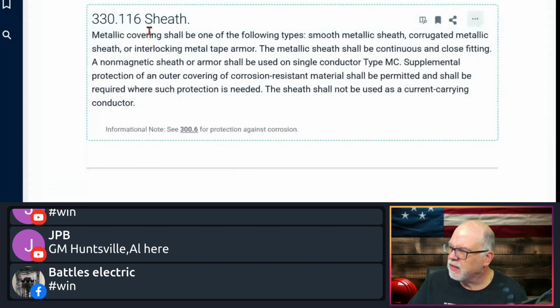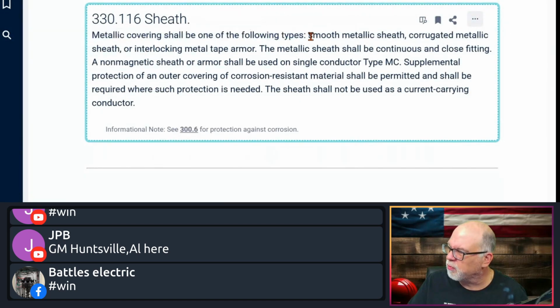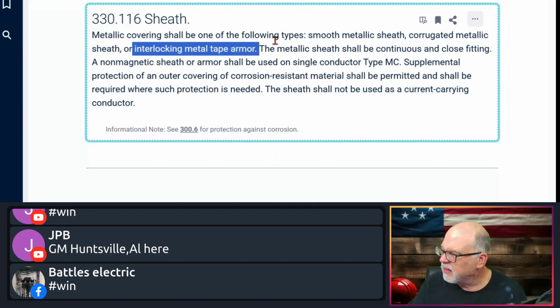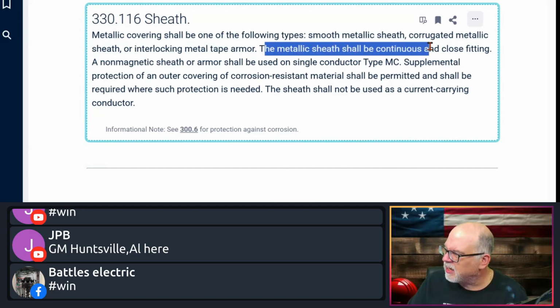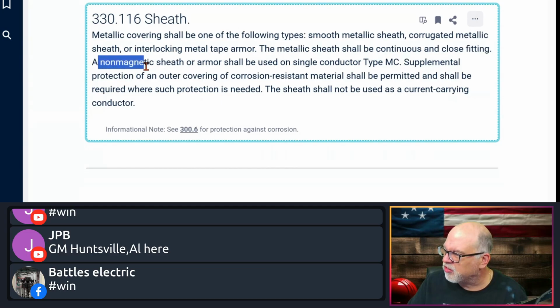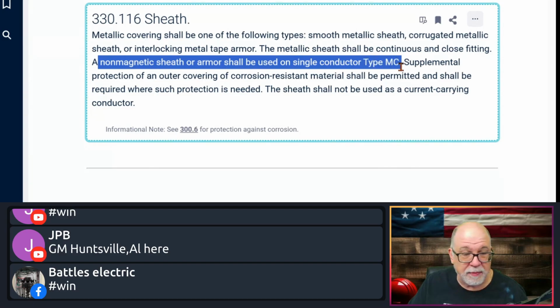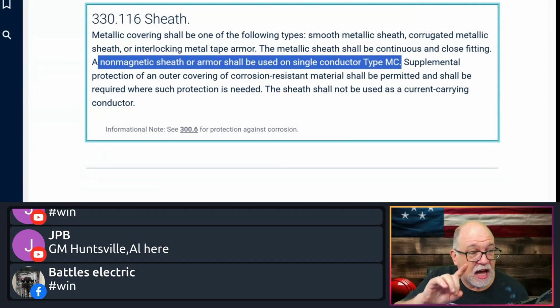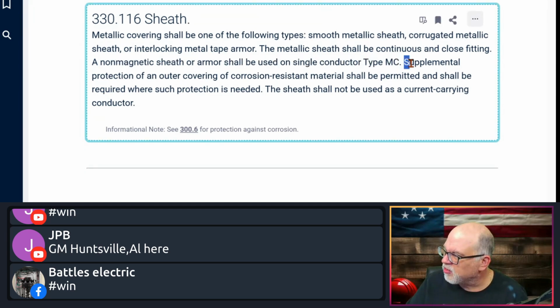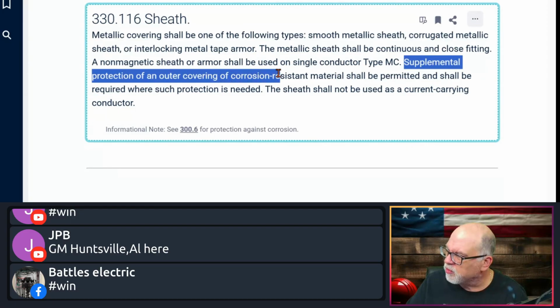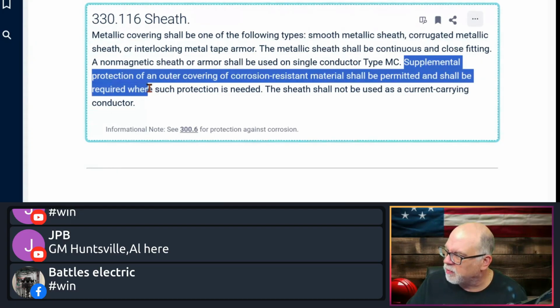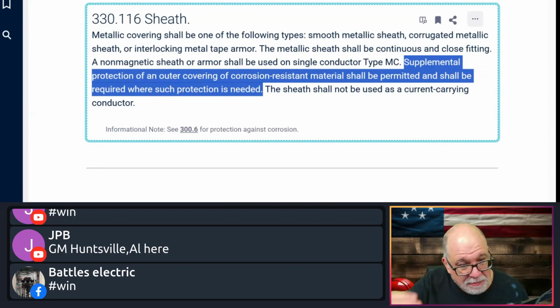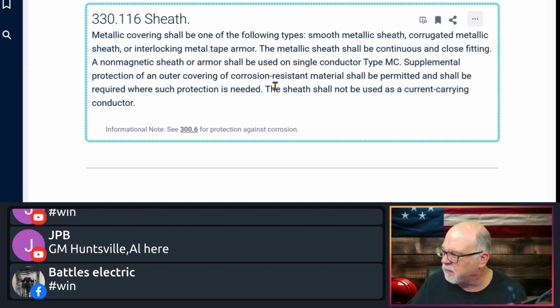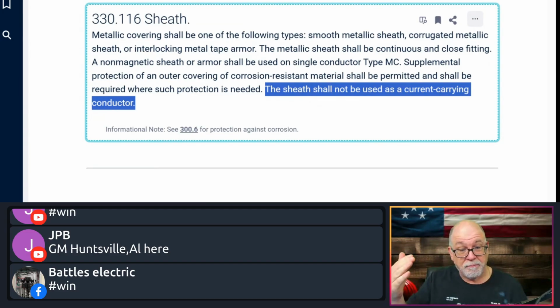Okay. The sheathing. The metal covering shall be one of the following: smooth metallic sheathing, corrugated metallic sheathing, or interlocked metal tape armor. I told you that at the beginning. Three different types. It says the metallic sheathing shall be continuous and close fitting. A nonmagnetic sheath or armor shall be used on single conductor type MC. So single conductor type MC is a nonmagnetic type, like aluminum. It says supplemental protection of the outer covering of corrosion resistant material shall be permitted and shall be required where protection is needed. That is the PVC jacketing material that is permitted to be extruded over the metal sheathing. It says the sheathing shall not be used as a current carrying conductor. Should be a no-brainer, but again, you'd be surprised.